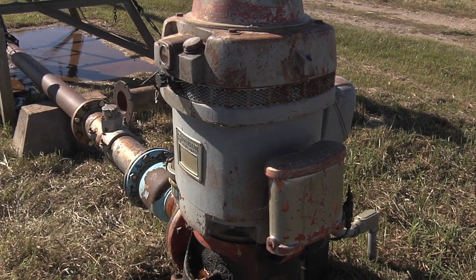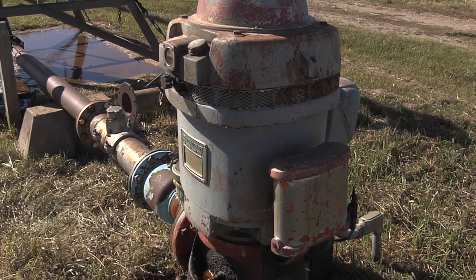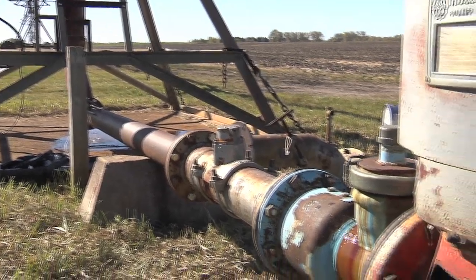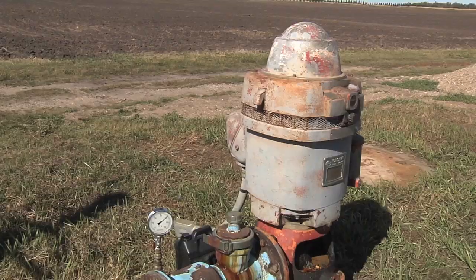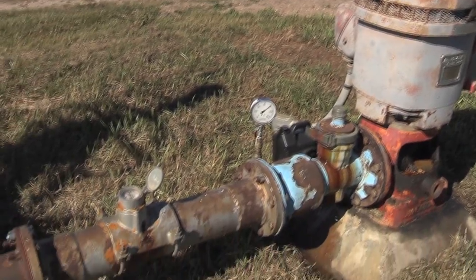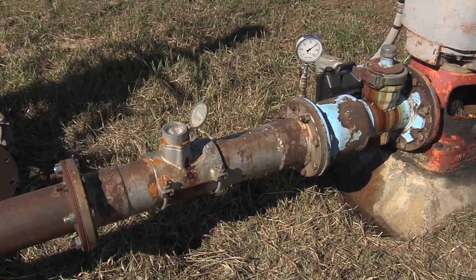The motor sounds very good. It was very quiet. Some were noisy. If there are any bearings going out, we didn't hear any of that. But I did some quick calculations, and this one's running at about 80 to 85% of standard. Now, there might be some reason. It's an old pump. There might be wear on the impellers. The impellers may not be adjusted properly. There are a number of reasons. It's certainly not due to the well, but the pump, because of age, probably needs some work.